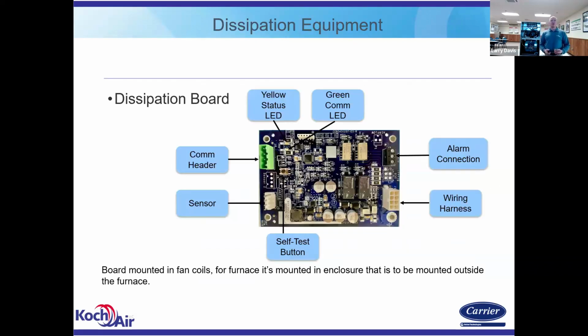Another good picture of the dissipation board, just a reminder, it's one board fits all, whether you're communicating or non-communicating service, or system rather, and you do have an alarm connection output. Matter of fact, I think it's probably the same slide as we looked at before. There is a wire harness that goes from the board to the sensor, and a wire harness that goes from the board to the furnace if it's a gas furnace application. If it's a fan coil, it's all internally factory mounted.